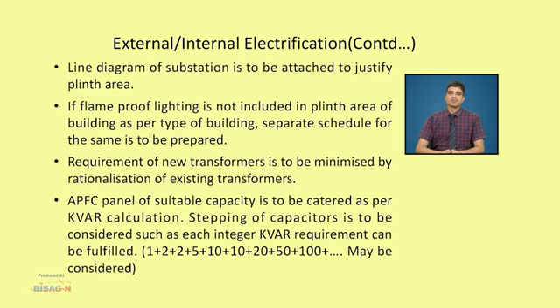Requirement of new transformers is to be minimized by rationalizing existing transformers. APFC panel of suitable capacity is to be catered as per kVAR calculation. Stepping of capacitor is to be considered such that each integer kVAR requirement can be fulfilled. One example can be taken as 1 plus 2 plus 2 plus 5 plus 10 plus 10 and so on and so forth.